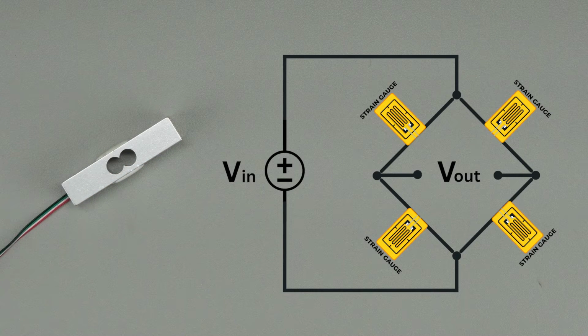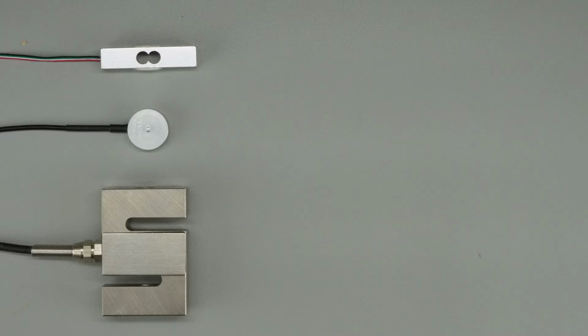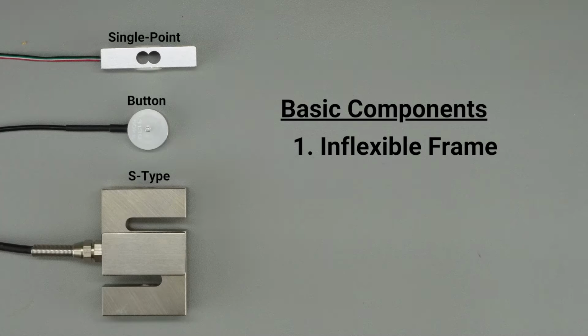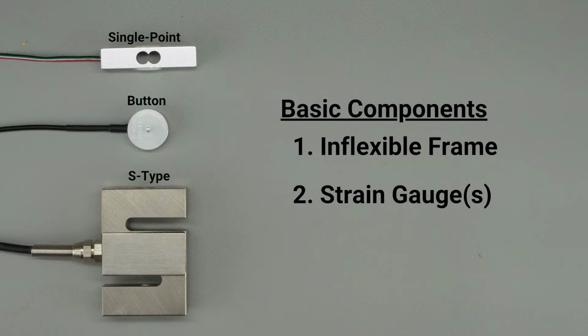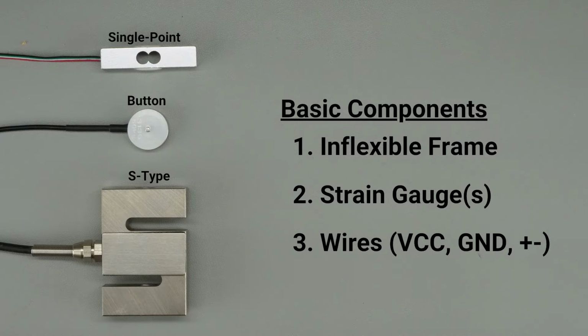Load cells like these typically use 4 strain gauges that are arranged in a Wheatstone bridge configuration. As the resistance value of the strain gauges change, the output of the Wheatstone bridge will also change. There are many different types of strain gauge load cells. A few are shown here. Each one has the same basic components: an inflexible frame or body, generally made of aluminum or a steel alloy, 1 or more strain gauges, and wires for power, ground, and signal.